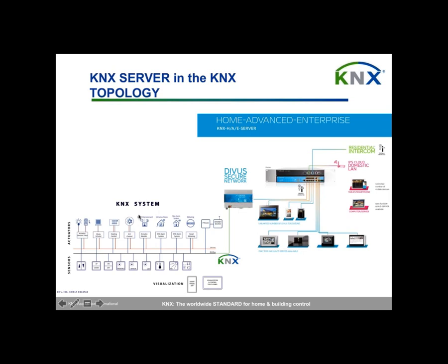I like this slide very much because you can see the real topology of our visualization system. Some of our customers say, okay, I want to control cameras. Can we control cameras with KNX? No, you cannot control cameras with KNX, but what you can do is show the image of the cameras in a visualization. For example, if the camera is connected to this switch, I can show it on this touch screen, on this touch panel, or on my phone. So this touch panel will be showing the cameras, controlling the security system, and also controlling the lights from the KNX side.